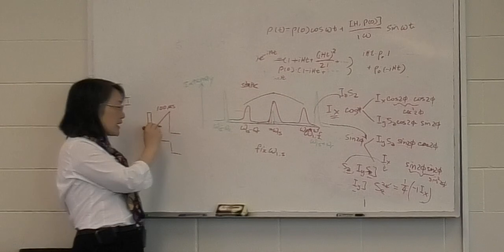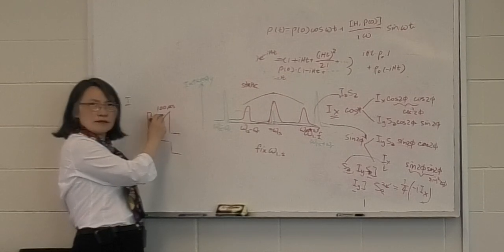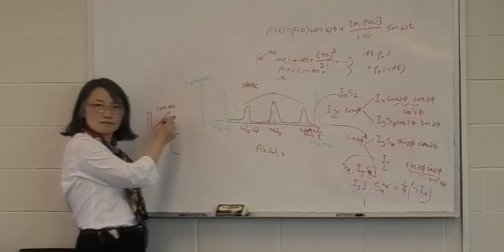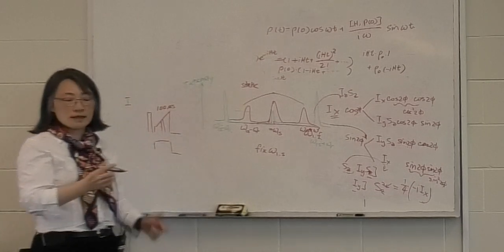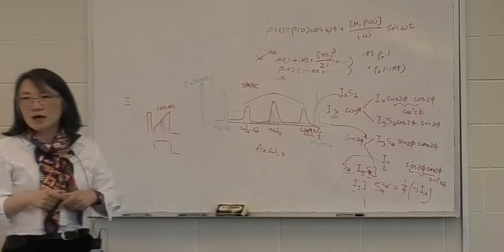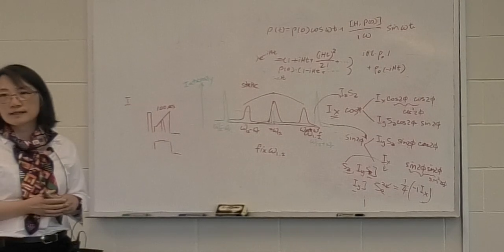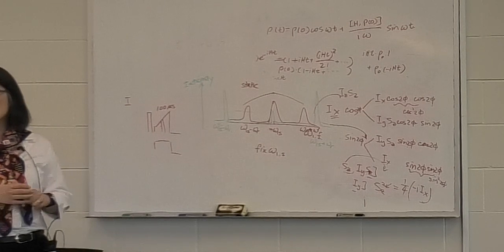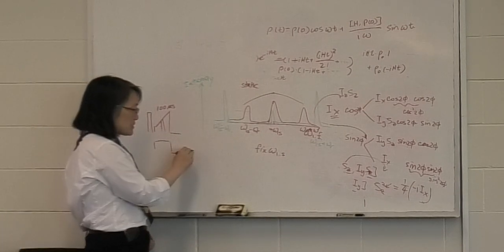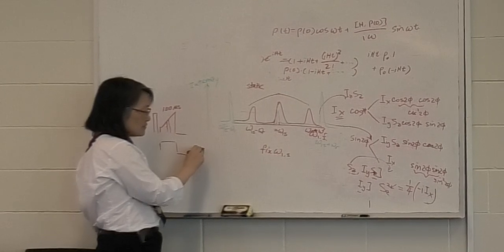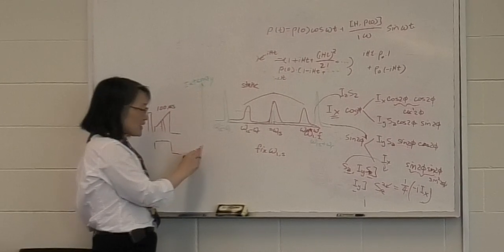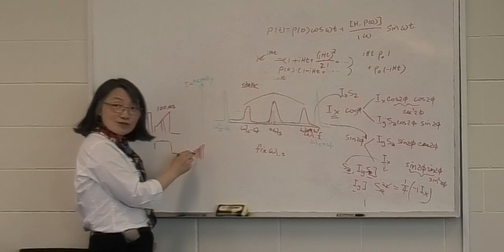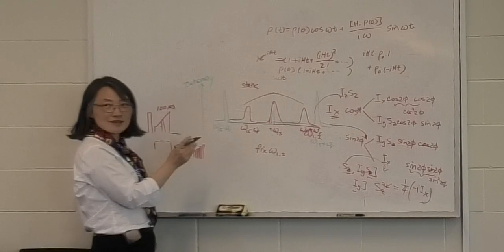So then I can choose a short CP contact time. And if I'm doing ramping, then maybe it only spends even a small fraction of a short CP contact time being correct. Then that's very difficult. When you do ramp CP, you want to have a moderately long contact time. And then instrumentation-wise, all of these ramps are piece-wise, right? So you have to think about what the digital resolution is, what's the shortest you can do. These days, it's not such a big deal.